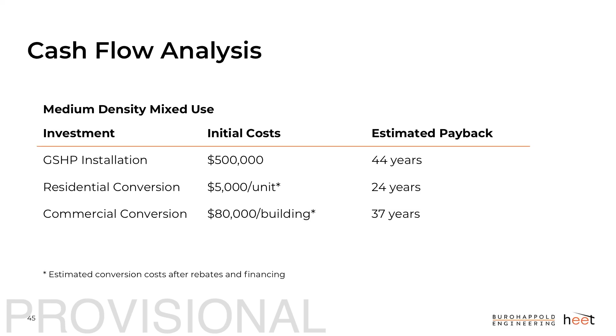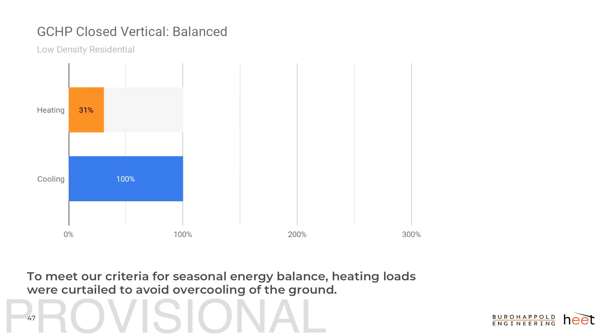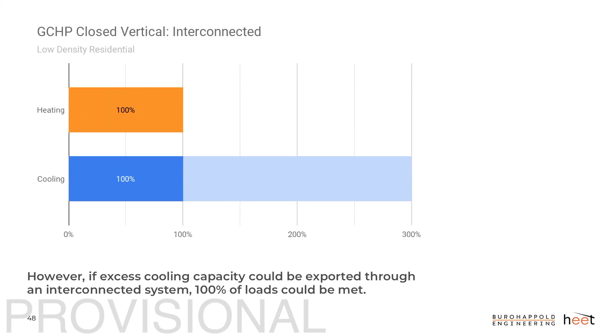So on the other end of the spectrum, for low density residential, when it's in a balanced condition, you can meet 100% of your cooling loads, but only about 30% of your heating loads. Whereas if you open it up again, you would meet both loads, but you'd have a significant amount of cooling energy to export in this case. And this could be taken off by something like an ice hockey rink, commercial cold storage, anything that would need cooling. So you could interconnect that type of use and make the system more feasible.